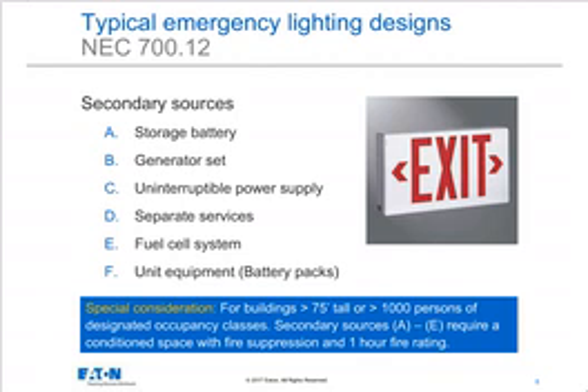Now, unit equipment, part F there, that's where they're talking about the wall mount exit signs, the wall mount emergency lights. In the blue box at the bottom of the slide, there is a special consideration that we should note. It says for buildings higher than 75 feet tall or buildings that house greater than 1,000 persons of designated occupancy, then secondary sources A through E, whether it's a storage battery, a generator, UPS, or whatever, are required to be located in a conditioned space with fire suppression and a 1-hour fire rating.